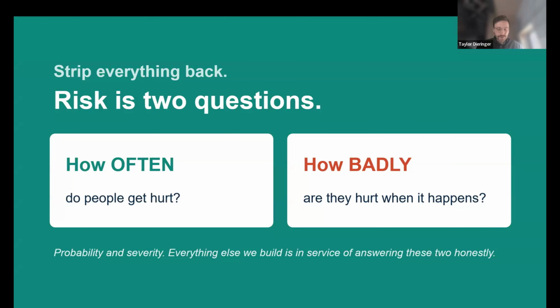And this is also something that I find the FDA can agree with. I've had experiences in the past where I've presented to the FDA and had a chance to speak with some of their personnel off to the side, and I just straight up asked, "What is your perspective of ISO 14971? Do you like it? Do you not like it?" Their response wasn't very positive. They identify ISO 14971 as something that can help you do risk management, but they also identify it as a means of manipulating probabilities in the post-market phase that is beneficial to the manufacturer.